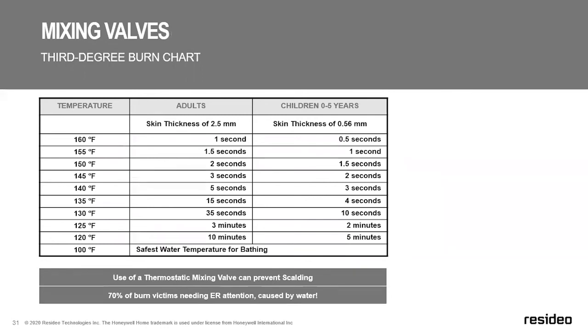So if you look at adults versus children, 0 to 5 years old, their skin is thinner than adults, so they will actually get scalded a lot quicker. And if you look at the temperature rating on the bottom of this chart, you have 100 degrees. That's the safest water temperature for bathing. When we increase that to 120, if you're an adult and you're exposed to that for 10 minutes, you'll be scalded. And as we go up by 5 degrees to 125, that goes down to 3 minutes.